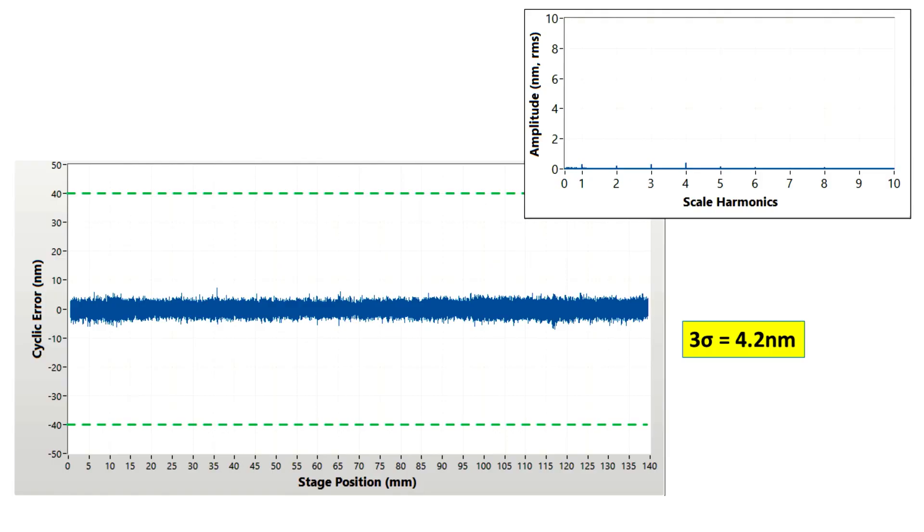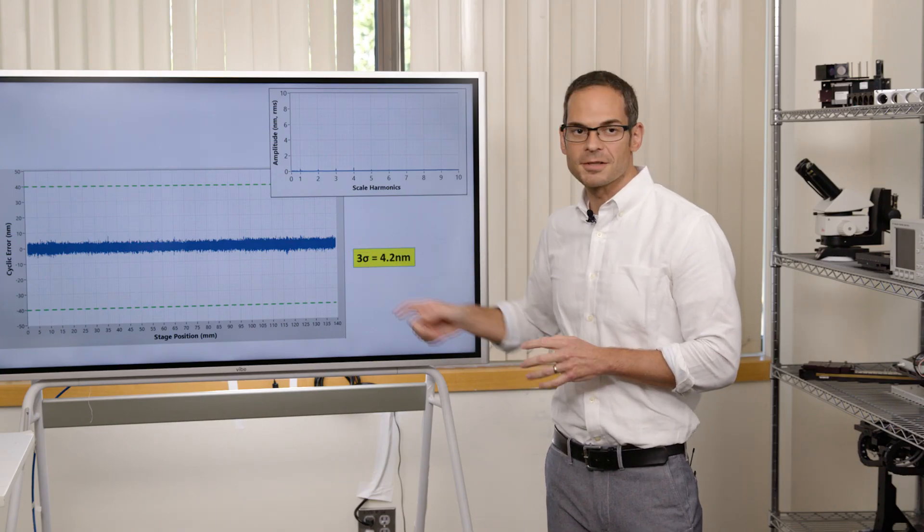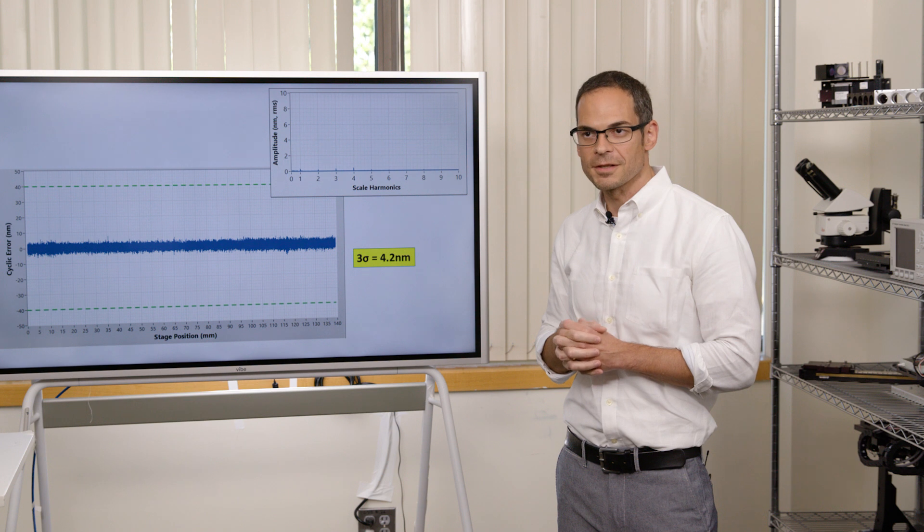So this is what good looks like. This is another stage from Dover Motion, where again, we've taken a laser interferometer, triggered from our hardware using TTL, and measured the inaccuracy of the encoder, the cyclic error specifically.